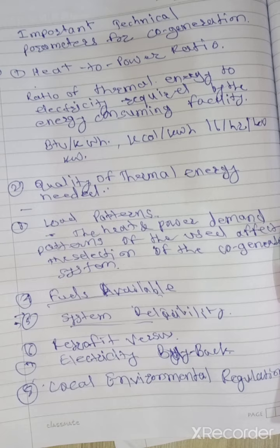The prime mover installed operates at full load at all times. If the electricity demand of the site exceeds that which can be provided by the prime mover, then the remaining amount can be purchased from the grid. Likewise, if local laws permit, the excess electricity can be sold to the power utility.